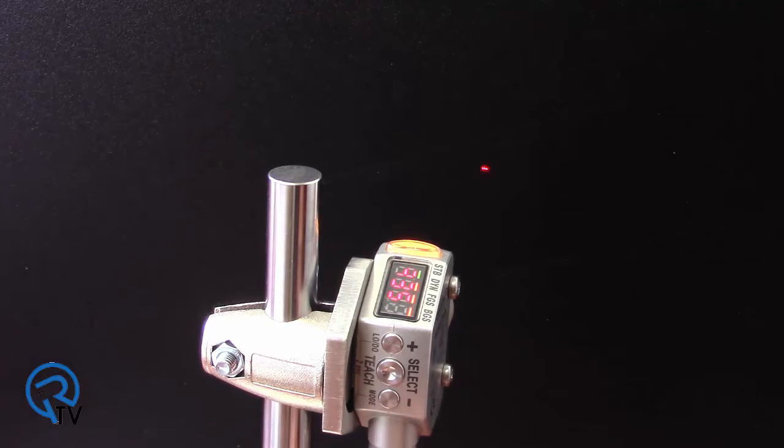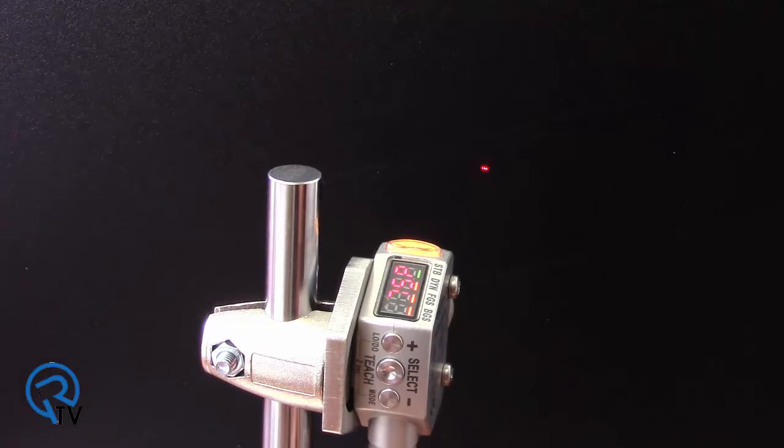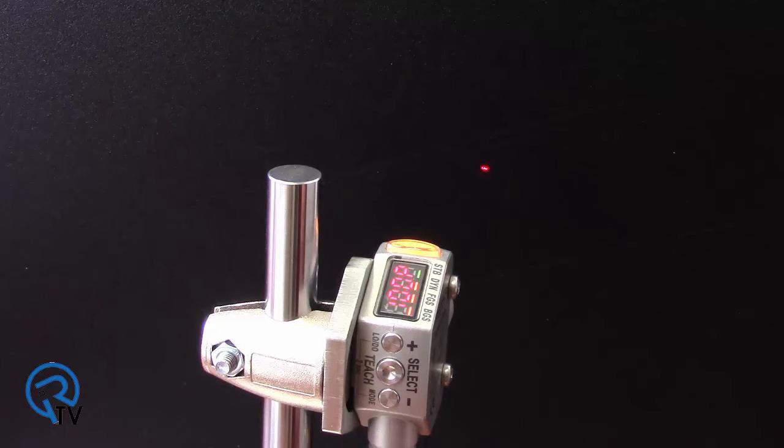Present a reference condition and push the Teach button again to teach the reference condition. The sensor learns this as a 100% match condition and will look for changes in distance, intensity, or second reflection condition.